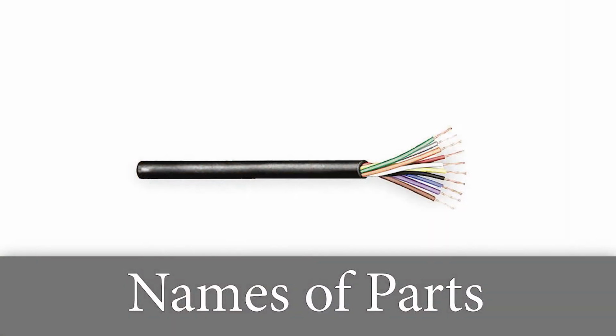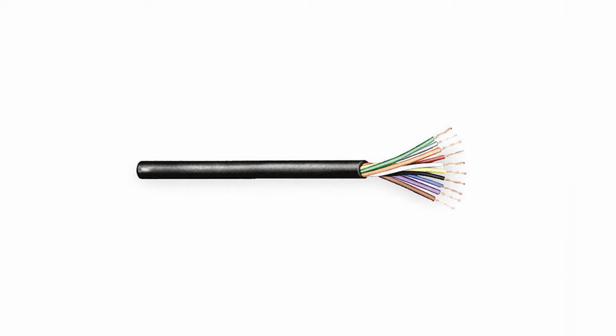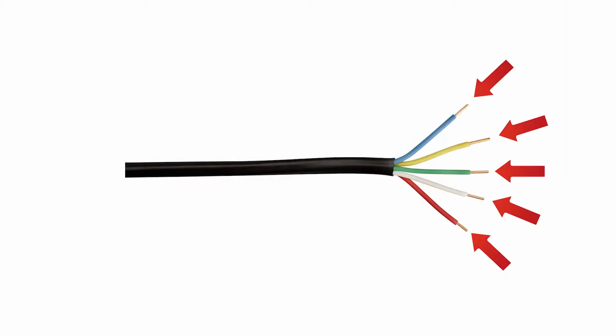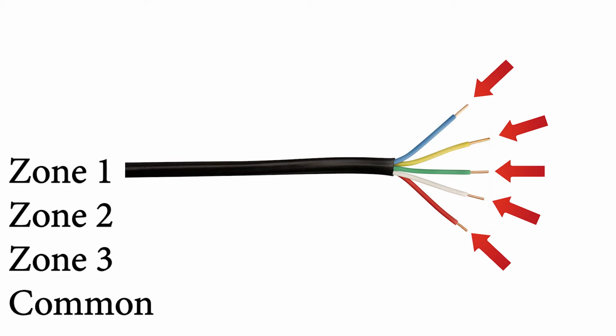Names of parts. Sprinkler wire is usually one wire bundle with many strands of smaller 18-gauge wire inside it. Wire strands usually come in 3 to 8 wires but can go up to 12 or more. You will always need one extra wire in the bundle than the number of valves. For example, if you have 4 valves, you will need a minimum of 5 strands of wire, with the 5th wire being the common wire.